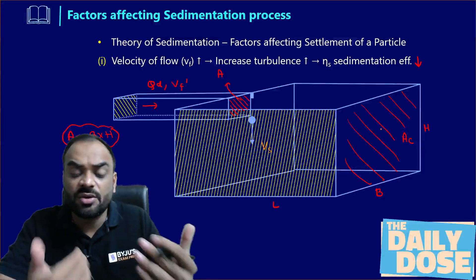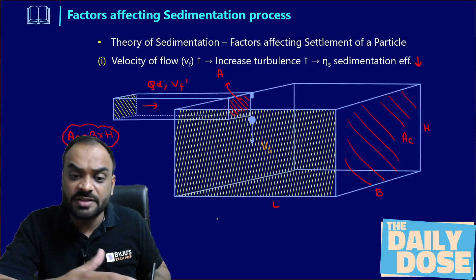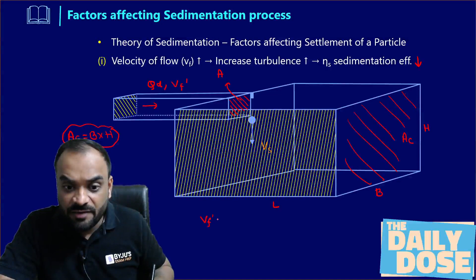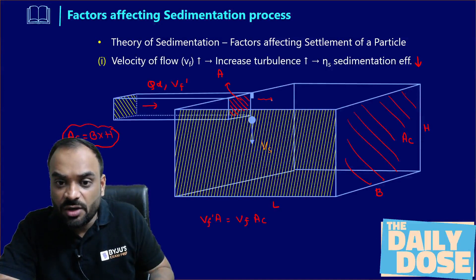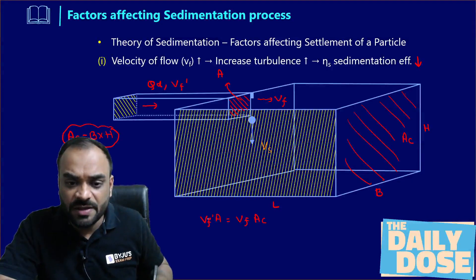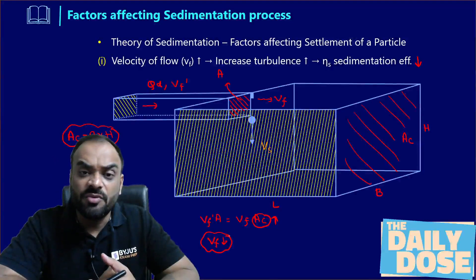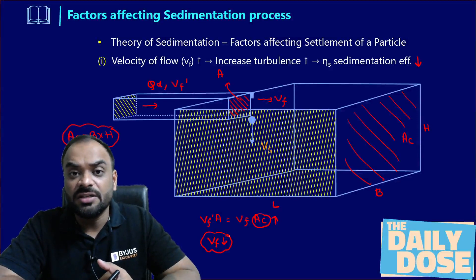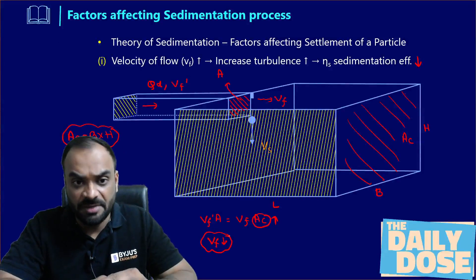If we suddenly increase the cross-section area of the sedimentation tank, the flow velocity will then reduce. Why? Because as per the continuity principle: VF' × A = velocity of flow in sedimentation tank × cross-section area AC. Since AC is very large, the value of VF will get reduced. By this, we are able to reduce the turbulence in the sedimentation tank so that the sedimentation process has more efficiency. This is one factor we have to address, and we are able to do it in the treatment plant easily.